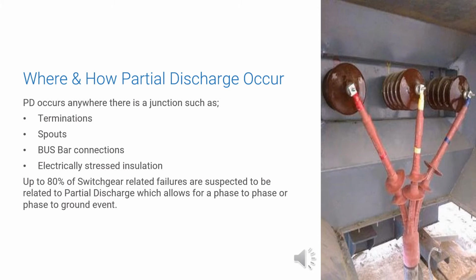Partial discharge occurs anywhere there is a junction, such as a termination, a spout, bus bar connection, or electrically stressed insulation. Up to 80% of switchgear related failures are suspected to be related to partial discharge events, which allows for a phase-to-phase or phase-to-ground event to occur, leading to an arc flash.